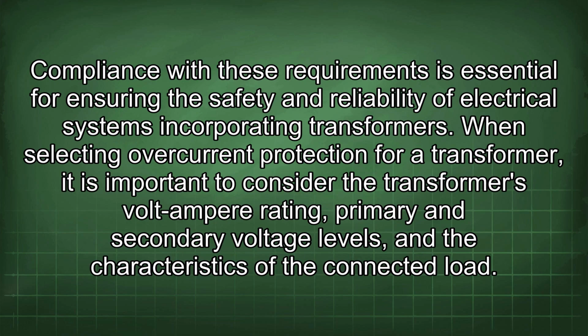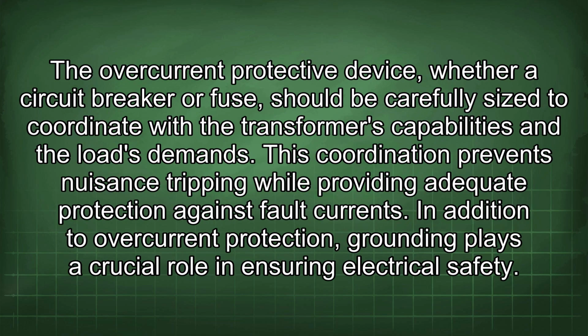Compliance with these requirements is essential for ensuring the safety and reliability of electrical systems incorporating transformers. When selecting overcurrent protection for a transformer, it is important to consider the transformer's volt ampere rating, primary and secondary voltage levels, and the characteristics of the connected load. The overcurrent protective device, whether a circuit breaker or fuse, should be carefully sized to coordinate with the transformer's capabilities and the load's demands. This coordination prevents nuisance tripping while providing adequate protection against fault currents.